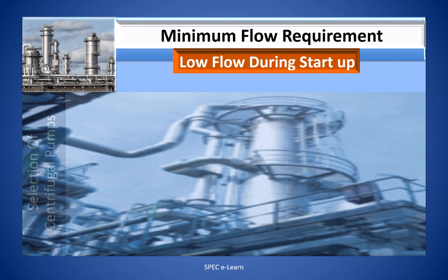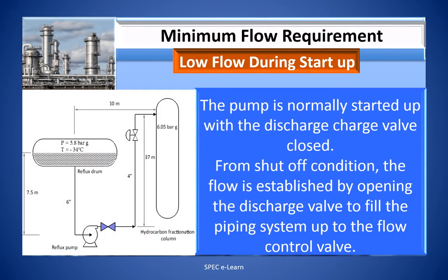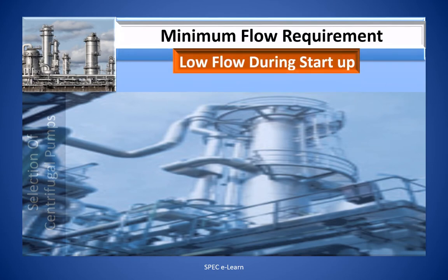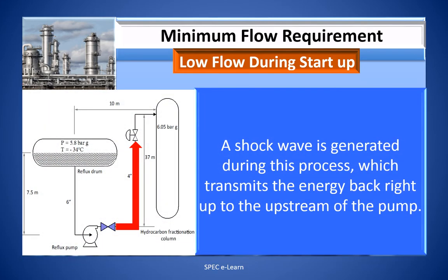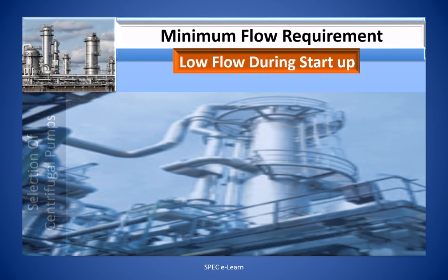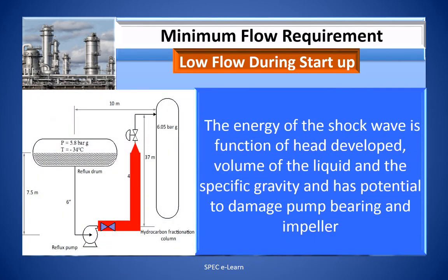The pump is normally started up with the discharge valve closed. From shut-off condition, flow is established by opening the discharge valve to fill the piping system up to the flow control valve. A shock wave is generated during this process which transmits energy back upstream to the pump. The energy of the shock wave is a function of head developed, volume of liquid, and specific gravity, and has the potential to damage pump bearings.